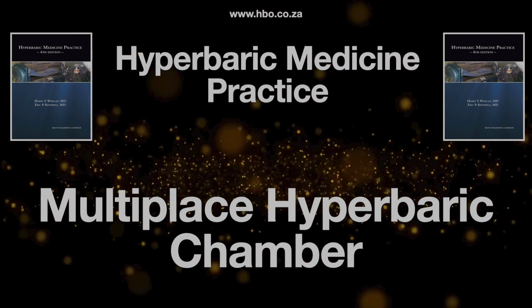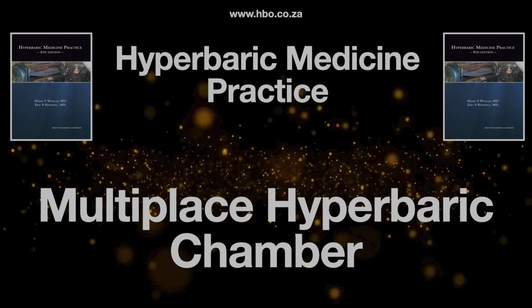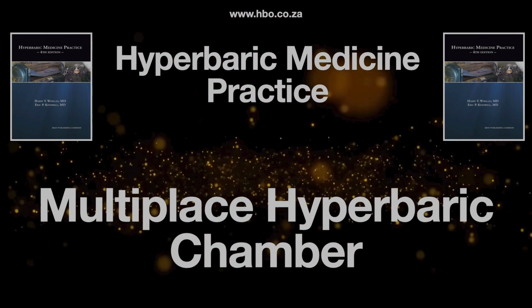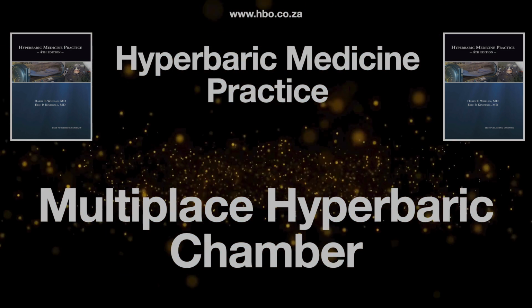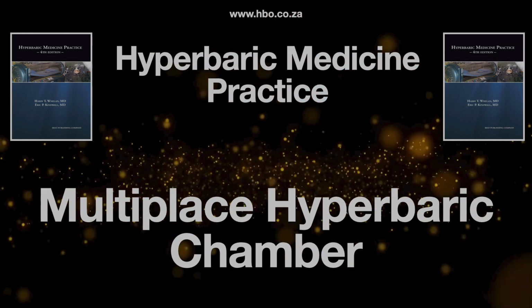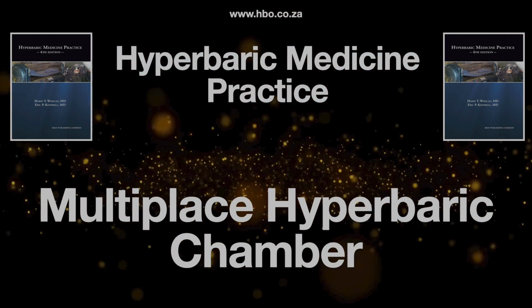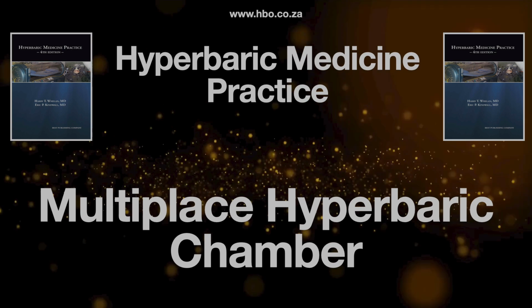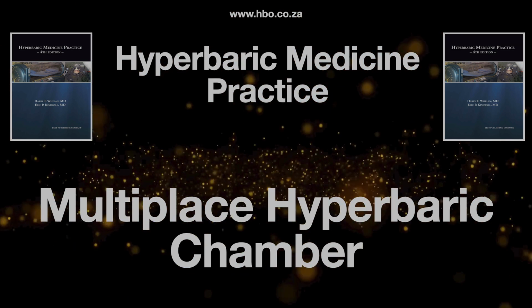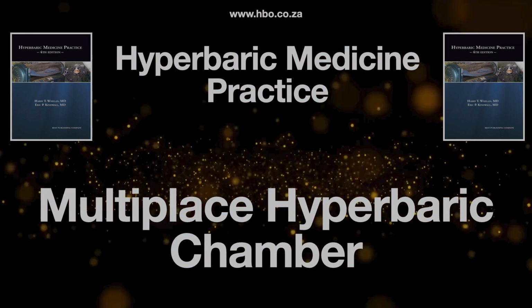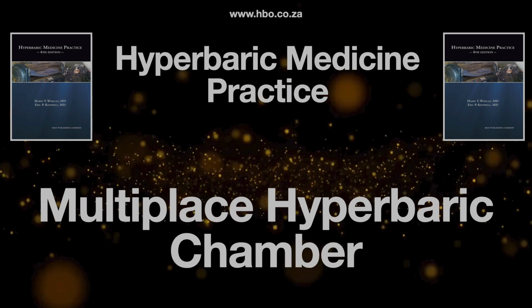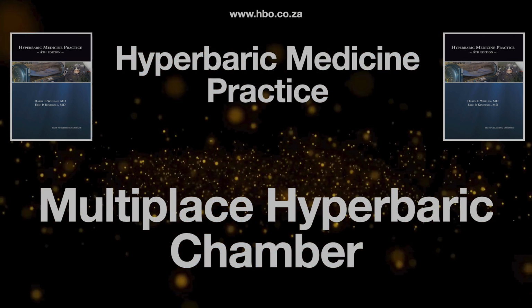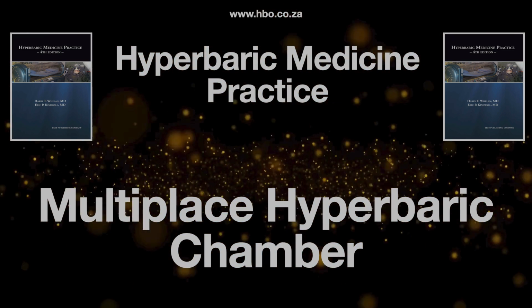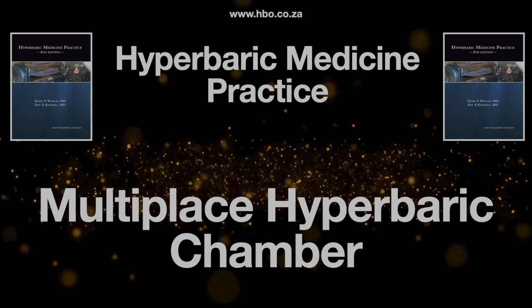Generally you've got 2 main parts connected. The big one is the main treatment chamber where patients get the therapy, and then there's a smaller attached compartment called an airlock. The airlock, like on a submarine, is absolutely vital, it's the transition zone. It lets staff get in and out of the main chamber without messing up the pressure inside, so you don't have to decompress the whole main room every time someone needs to enter or leave.